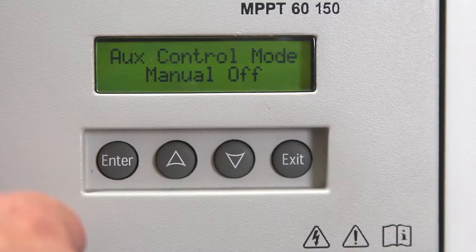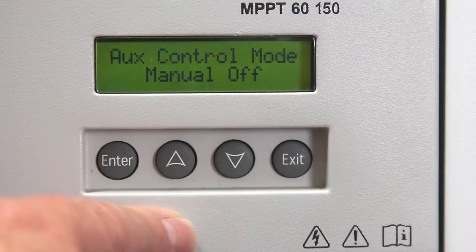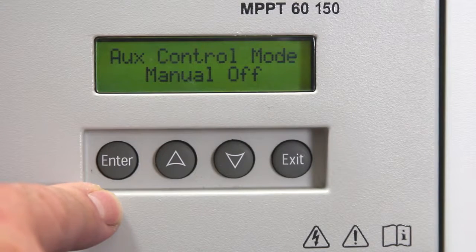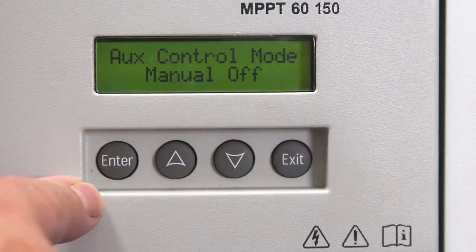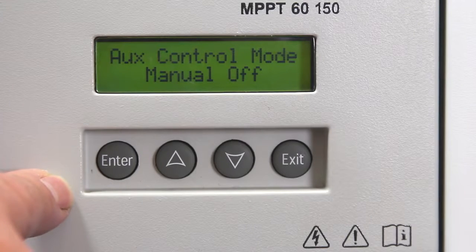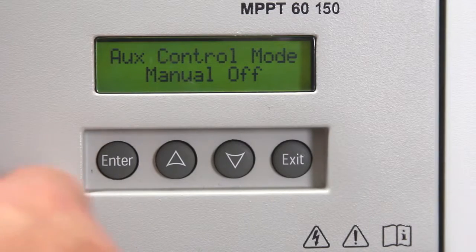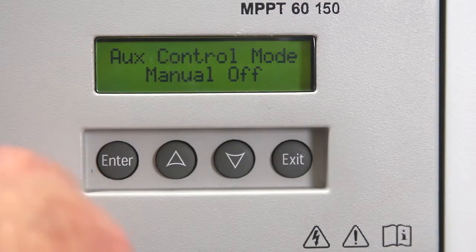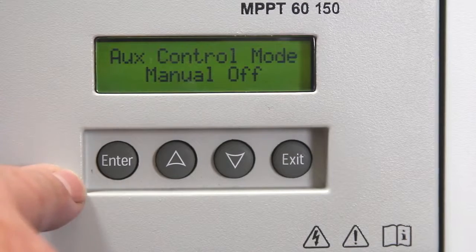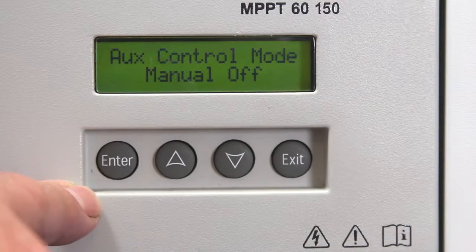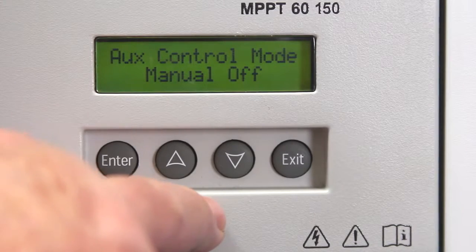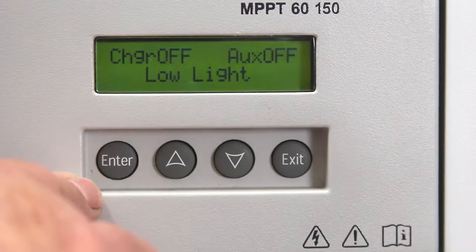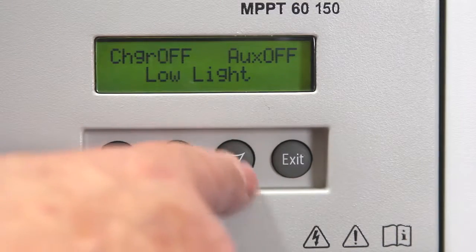Auxiliary menu. Auxiliary is for controlling the auxiliary port, which can be set from 0 to 12 volts DC and provide up to 200 milliamps to drive an external relay, or even start a generator in some cases. That would be a simple 2-wire configuration. You wouldn't have the cool down and crank time and all the specific generator related functions that are available through the AGS, so be careful there.